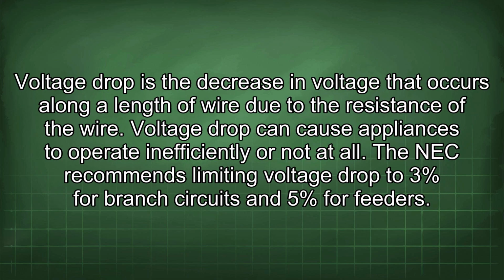Voltage drop is the decrease in voltage that occurs along a length of wire due to the resistance of the wire. Voltage drop can cause appliances to operate inefficiently or not at all. The NEC recommends limiting voltage drop to 3% for branch circuits and 5% for feeders.